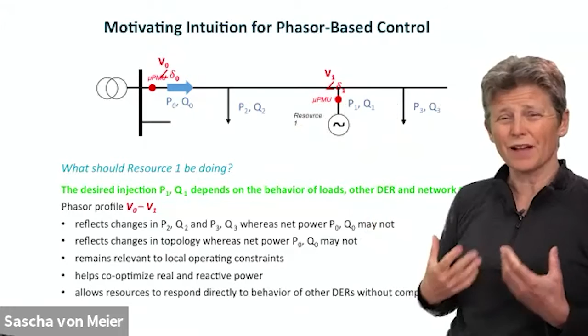So we're getting more locational information in that phasor. We're also able to observe changes in topology—if there are switching operations that might affect what is a safe operating state, you would be able to observe that in the phasor, but not by just measuring the net current. We're also able to address both real and reactive power. And again, we're not compromising privacy, because you can measure these phasors near a node and get the same answer without having to put a current transformer or current sensor on the circuit branch belonging to an individual customer.